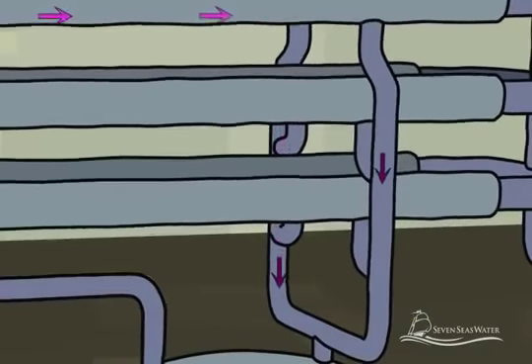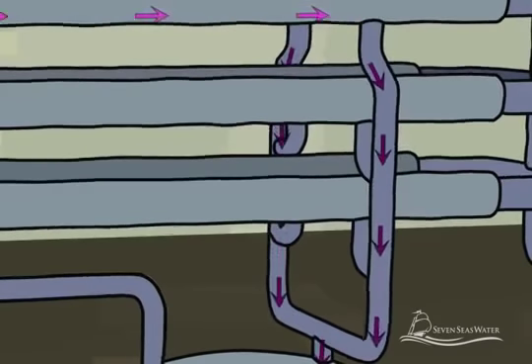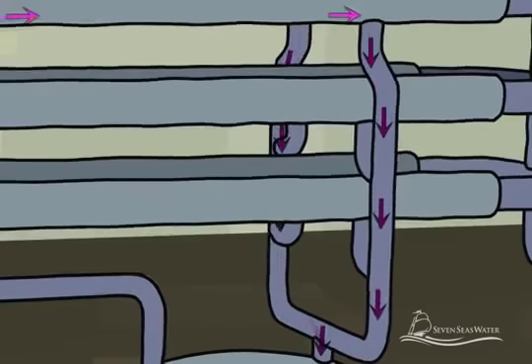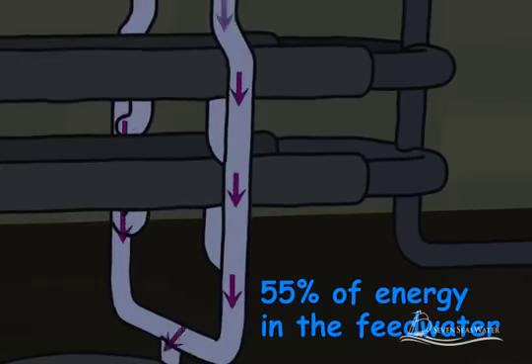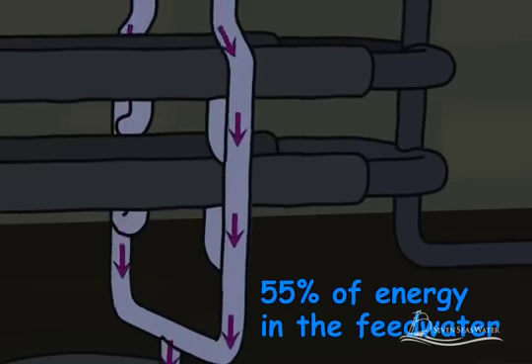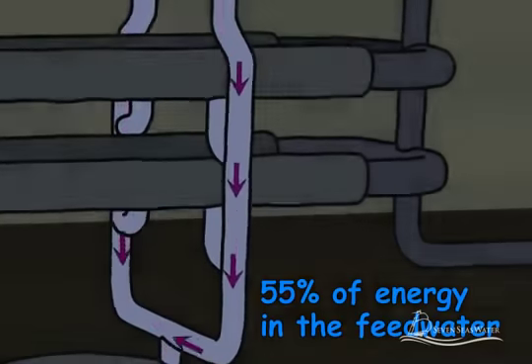The concentrated salt stream that is rejected from flowing through the membrane continues to pass across the membrane surface where it is collected separately. The concentrated salt stream retains about 55% of the total energy of the seawater stream that was originally fed to the membranes.